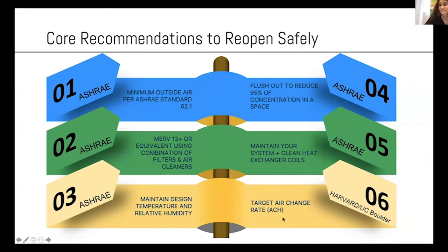Number six is target air exchange rate. I don't remember the name of the engineer that asked about this. Typically in ASHRAE standard 62.1, for commercial, educational, retail, and gym buildings, we use CFM per square foot plus CFM per person, as Dr. Shaza mentioned. For this pandemic, Harvard and UC Boulder introduced one more metric, which is air exchange rate. Typically, we only have air exchange rate in hospitals, standard 170.